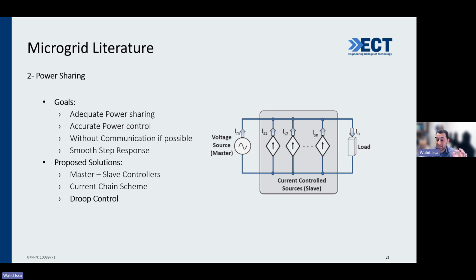But the most popular one, which doesn't need any communication, is called droop control. It relies on the frequency of the bus: if the frequency is lower, inverters push more power; if higher, they push less power; and if it's above some limit, they export even less. So the frequency of the bus acts as a communication signal between the inverters, without them actually communicating—no communication module needed. Droop control is very popular and robust, and it enables what's called hot swap plug-in inverters, so you don't need to communicate with others—you can just turn on your breaker, and that's it.